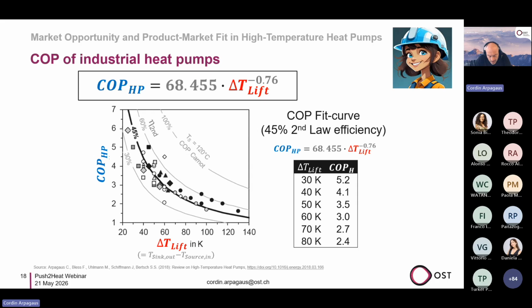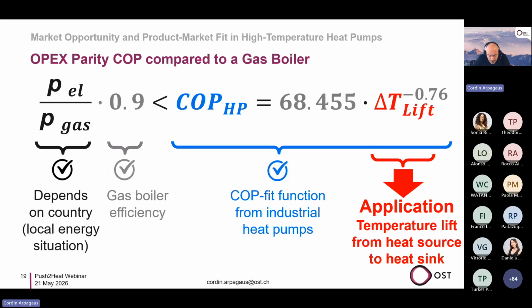This fit curve is representative for many industrial heat pumps. And it's the curve showing the COP as a function of the temperature lift. So the temperature lift between the heat source and the heat sink in the application. And this is about almost a 50% Carnot efficiency. So with this fit curve, we can connect the efficiency of the heat pump to the application, to the temperature lift. And now to find a business case, we have this very simple formula.